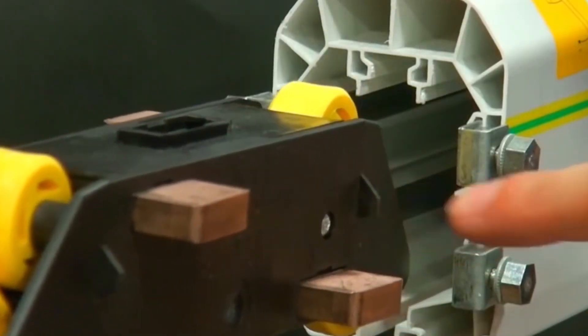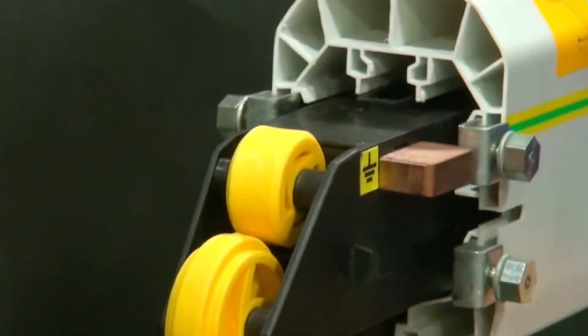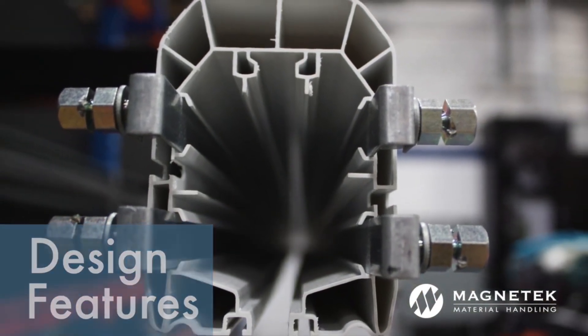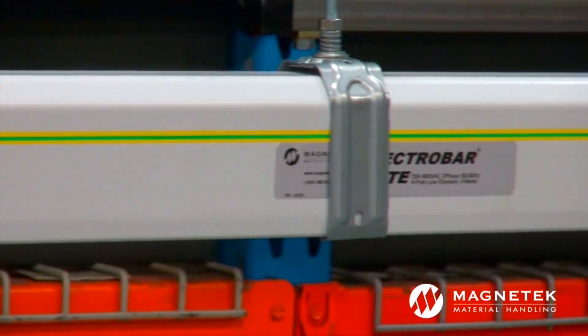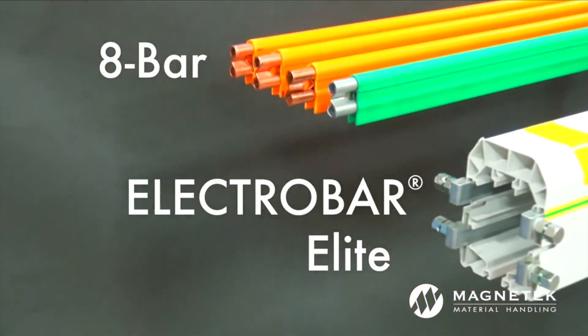A trolley stop feature also makes accidental backwards installation impossible, preventing phase-to-ground contact. ElectroBar Elite's cellular structure combines enhanced rigidity with reduced weight, so fewer hangers are necessary. Its compact design allows for installation in tight spaces where other systems won't fit.